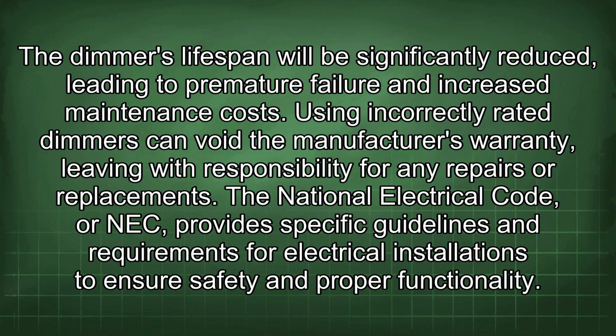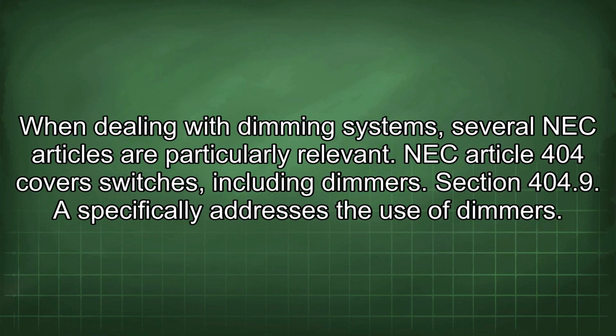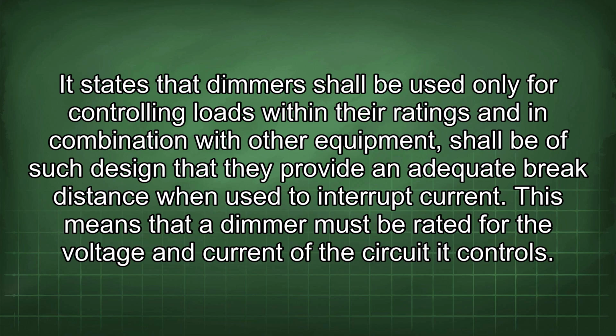The National Electrical Code, or NEC, provides specific guidelines and requirements for electrical installations to ensure safety and proper functionality. When dealing with dimming systems, several NEC articles are particularly relevant. NEC Article 404 covers switches, including dimmers. Section 404.9 specifically addresses the use of dimmers. It states that dimmers shall be used only for controlling loads within their ratings and in combination with other equipment shall be of such design that they provide an adequate break distance when used to interrupt current.